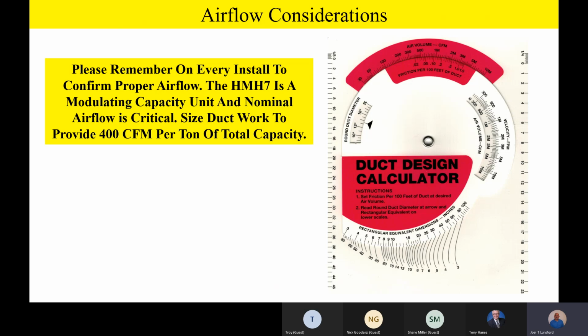So this is very, very important. Now, one of the reasons we have to remember this is on modulating units especially. Airflow is so important on every unit. But on modulating units, and this is just a general statement for any modulating piece of equipment, especially the HMH7, because it has multiple sensors on the refrigeration circuit. It's looking at suction line pressure. It's looking at suction line temperature. It's looking at liquid line temperature. I think it even looks at discharge line temperature and outdoor ambient temperature. So it's taking all those temperatures and information, and it's figuring out where it needs to be for capacity modulation.